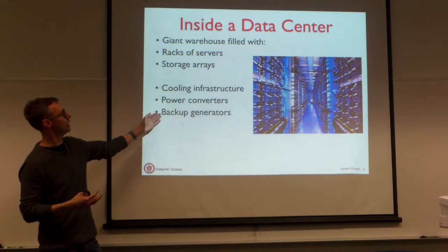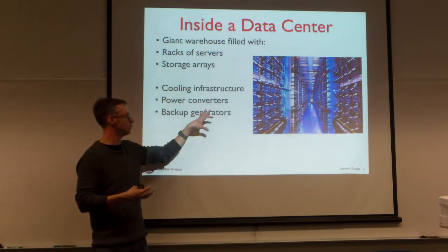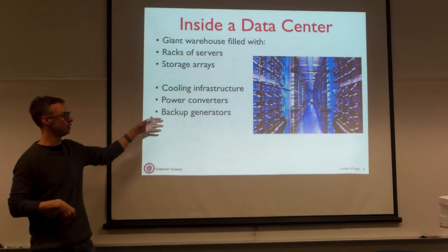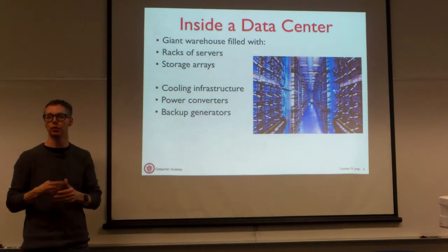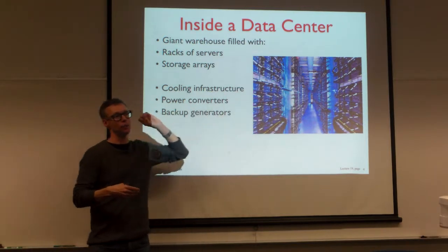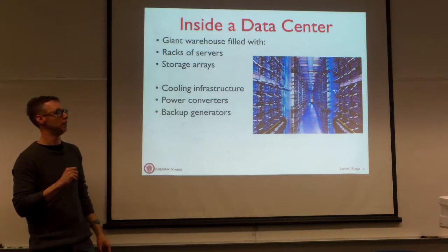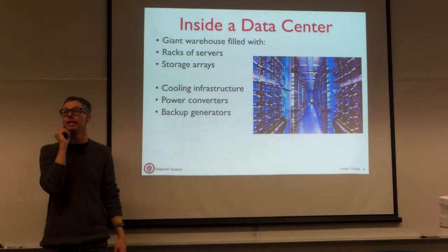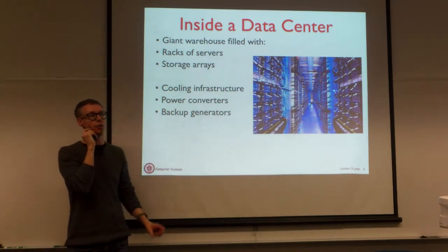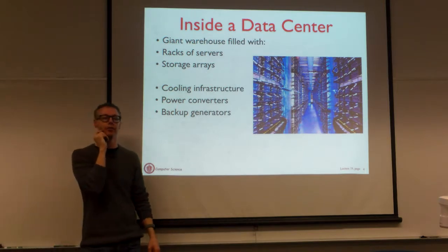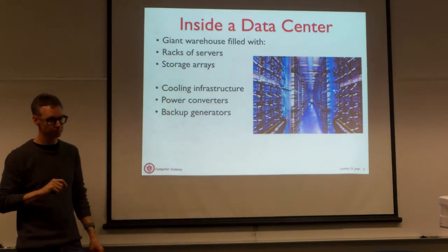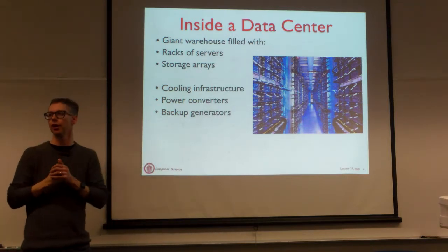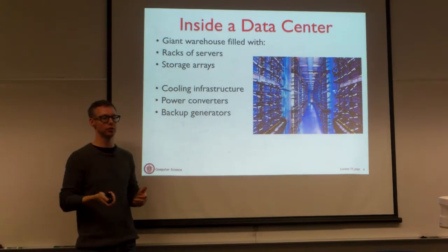And if you want to keep it running all the time, there's a lot of specialized infrastructure in the data center to make sure that happens. Oftentimes you'll have UPSs, uninterruptible power supplies, in the racks, so batteries in the racks for when they get cut off from power. You'll have backup generators on site. At the MGHPCC, I think they have a couple of diesel generators that can power a fraction of the data center, 20% of it, if it loses power. So you have all of this electrical and cooling infrastructure that goes into powering these servers.